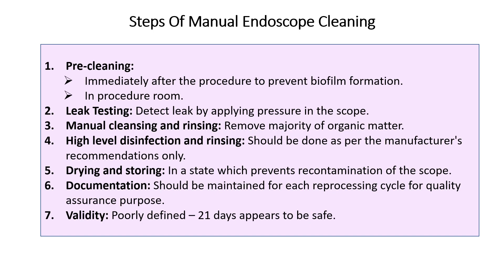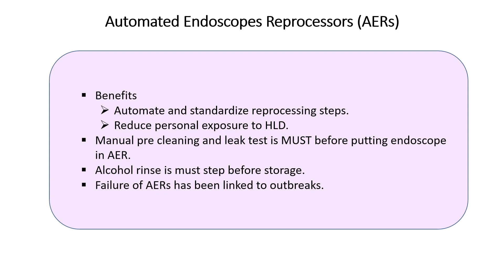The benefits of automated endoscope reprocessors are that they automate and standardize the reprocessing steps and reduce personnel exposure. Manual pre-cleaning and leak test is a must before putting the endoscope in automated endoscope reprocessors. Alcohol rinse is a must step before storage. Failure of the automated reprocessor has been linked to outbreaks. Thanks.